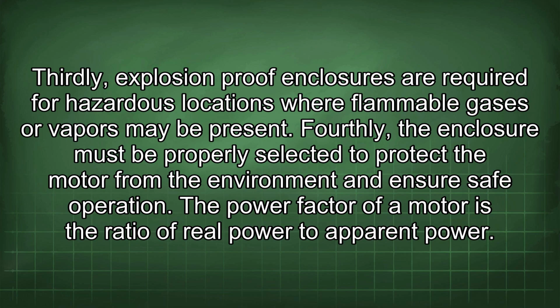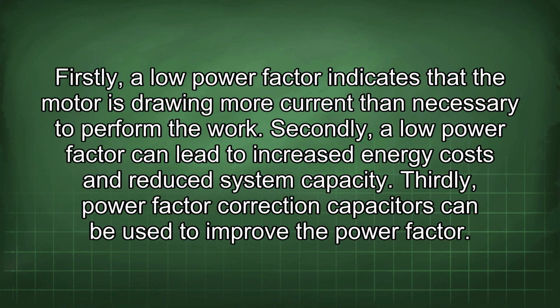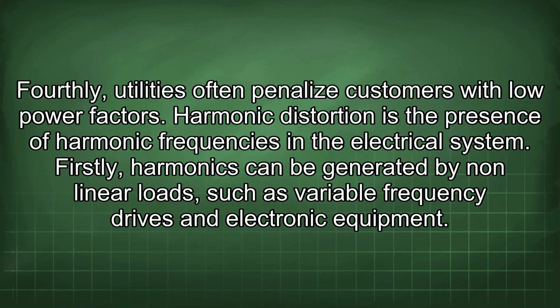The power factor of a motor is the ratio of real power to apparent power. Firstly, a low power factor indicates that the motor is drawing more current than necessary to perform the work. Secondly, a low power factor can lead to increased energy costs and reduced system capacity. Thirdly, power factor correction capacitors can be used to improve the power factor. Fourthly, utilities often penalize customers with low power factors.